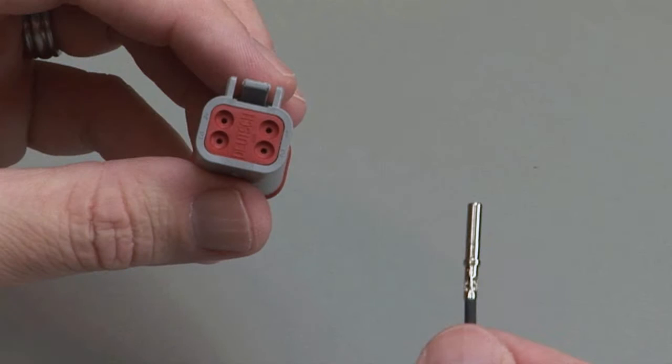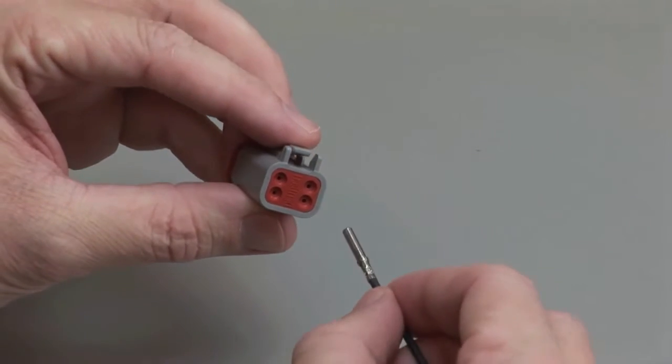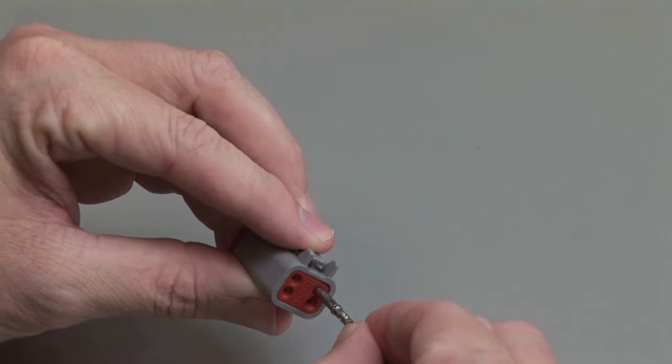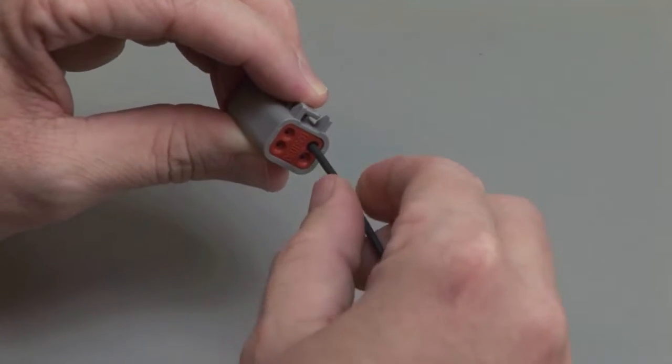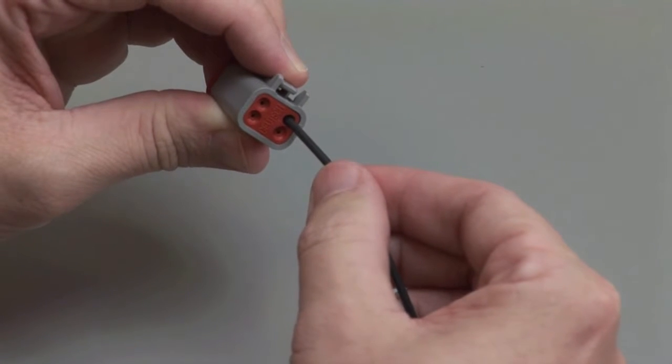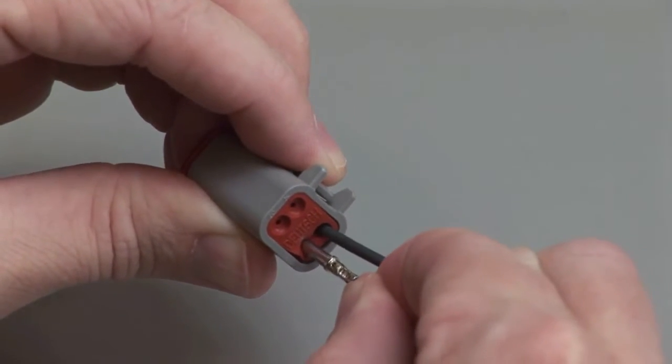Grasp the crimped contact approximately 1 inch behind the contact barrel. Hold the connector with the rear grommet facing you. Push the contact straight into the rear grommet until you hear and feel a click. A slight tug will confirm that the contact is properly locked into place. Repeat this process until all of the cavities are filled.